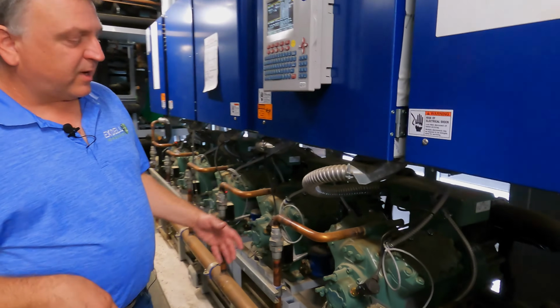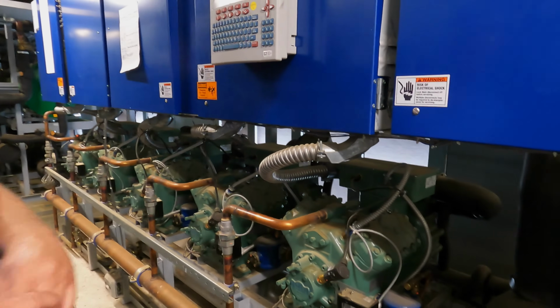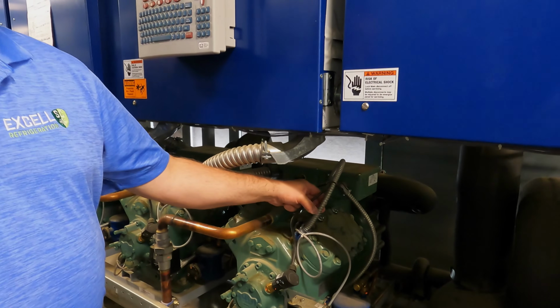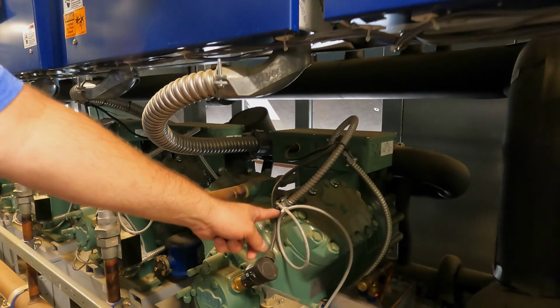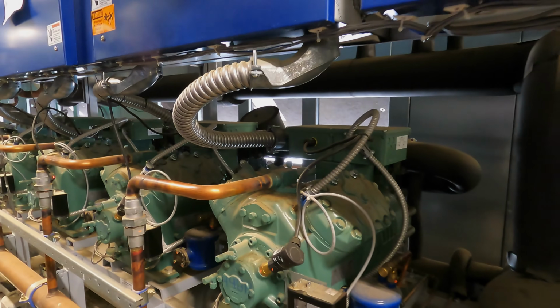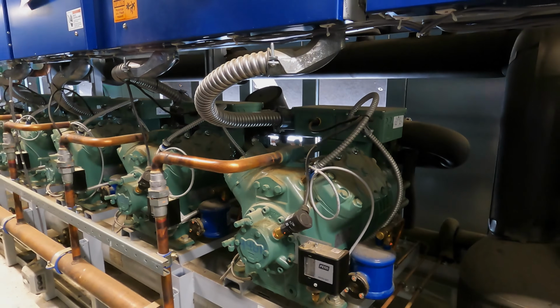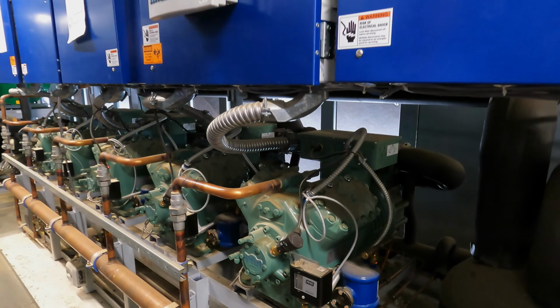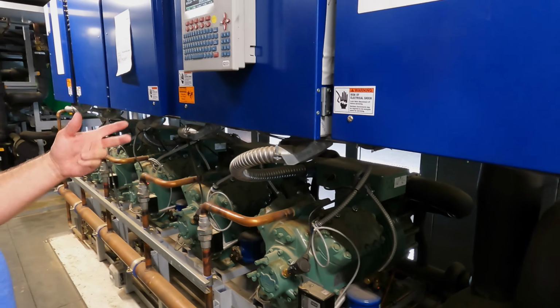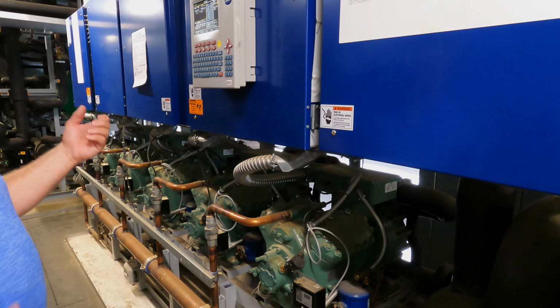So on these compressors, of course, we're going to have a lot of safeties. This is going to be our high pressure safety. This one's set for 345. So when the pressure gets above 345 pounds, it's going to open up the control circuit going to the contactor and shut it off.